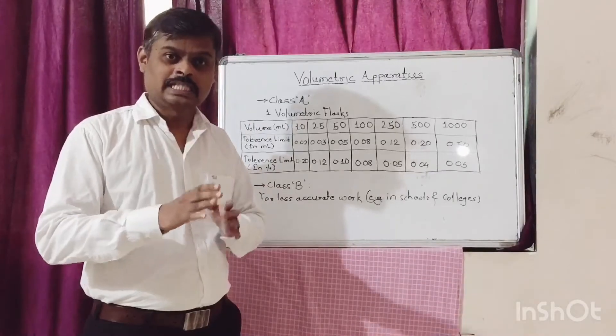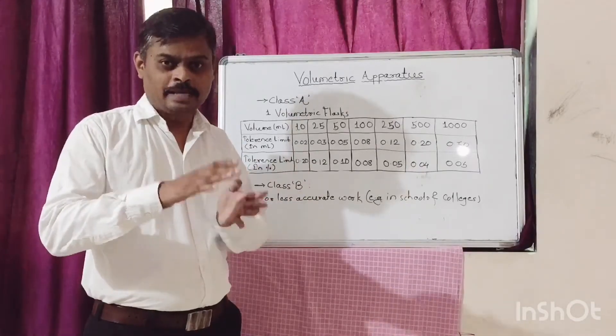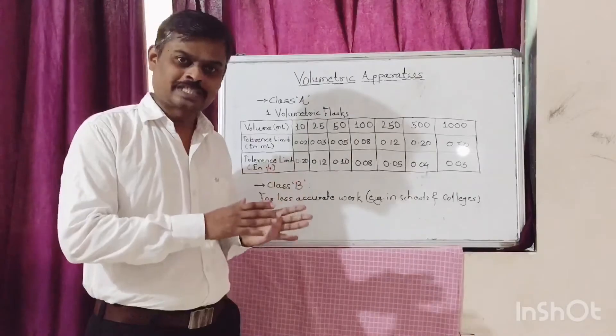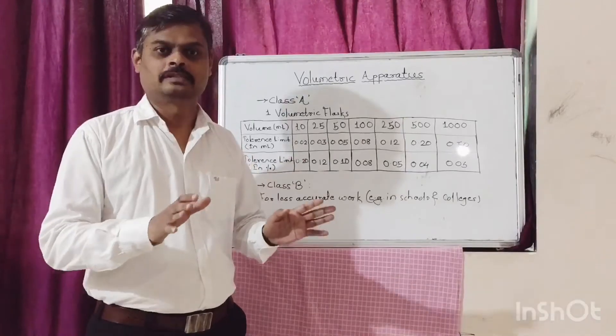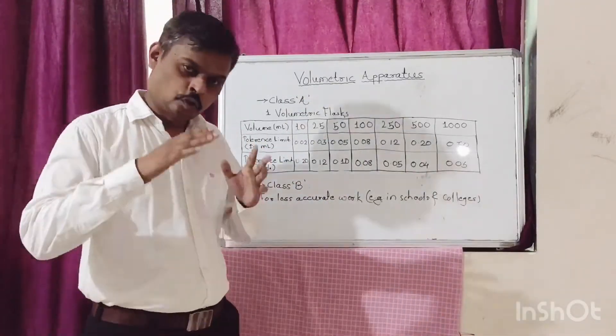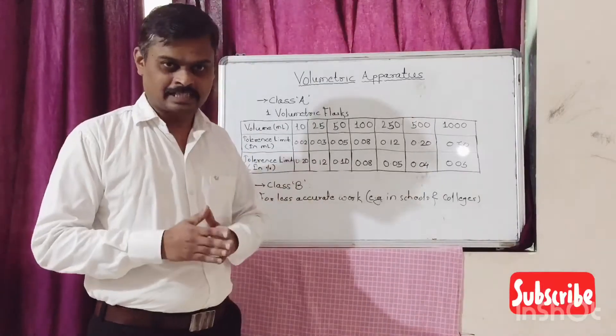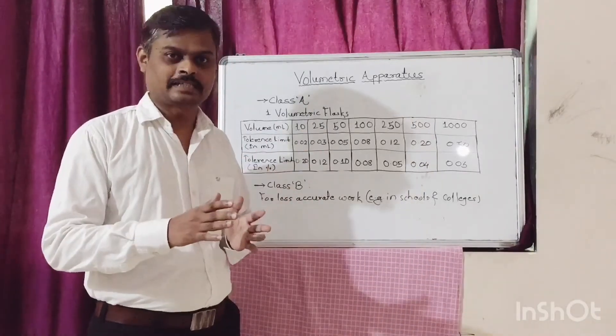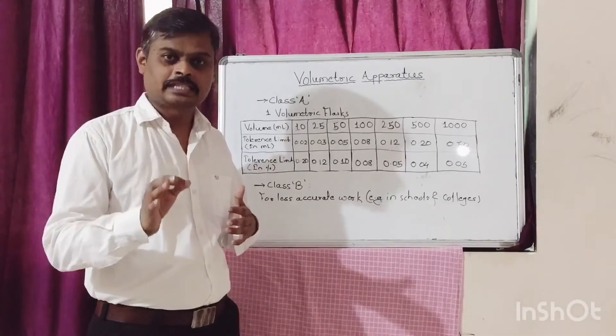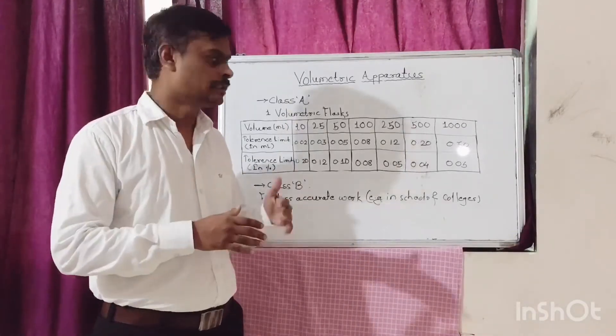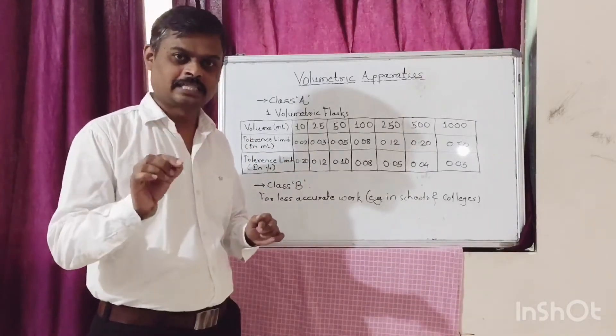Class A glassware does not require further in-house calibration before putting it into routine use. You can use Class A glassware directly for your analysis without further calibration in the laboratory. The tolerance limits for Class A glassware should comply with the standards mentioned by NIST, that is, National Institute for Standards and Technology, and ASTM E694.